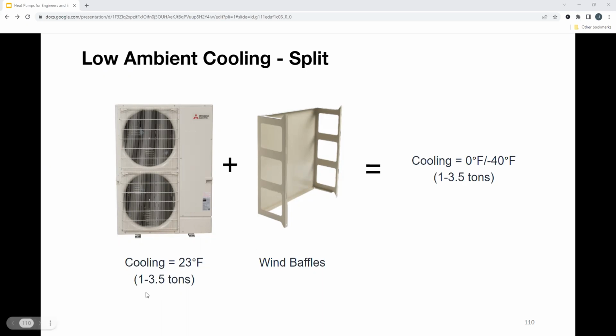But we have options between 1 to 3.5 tons. And now if you just select this and you don't include wind baffles, you're getting about 23 out of it for cooling. After that, you don't really get much cooling capacity out of it. The wind baffles protect it, add basically a coat on, and you are able to cool to 0 degrees, all the way down to negative 40 degrees for an application like that. That's your low ambient cooling split.